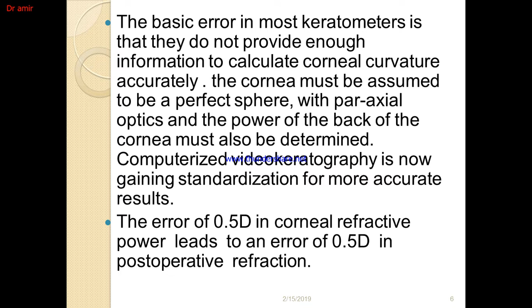Okay, in manual keratometry we use special equipment, and it has an eyepiece. We focus our eyepiece until we see the plus sign clearly. We take three measurements of the cornea, and we take the average of them. But the most important thing for the surgeon is this: if the power of the cornea is less than 40 diopter or more than 48 diopter, we discard that measurement from the technician.